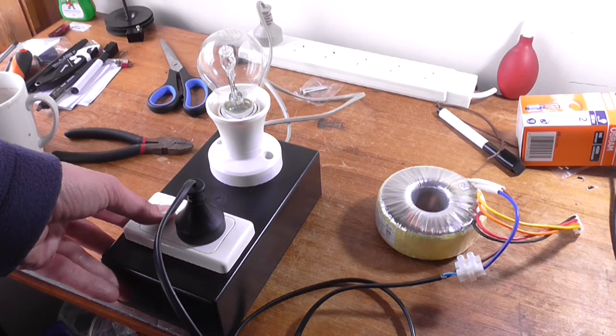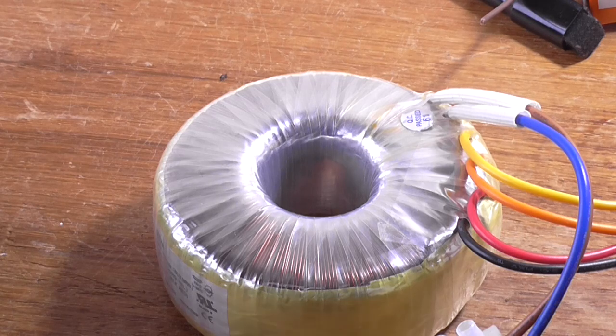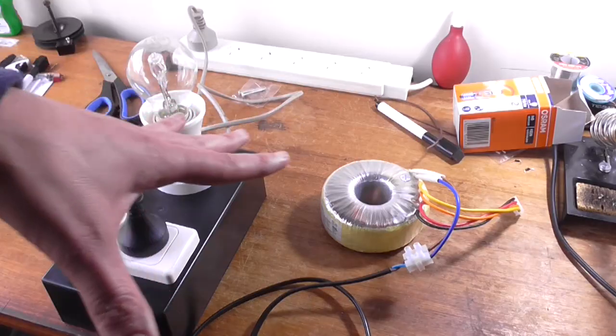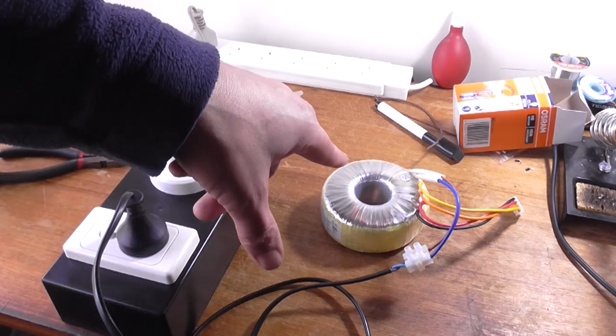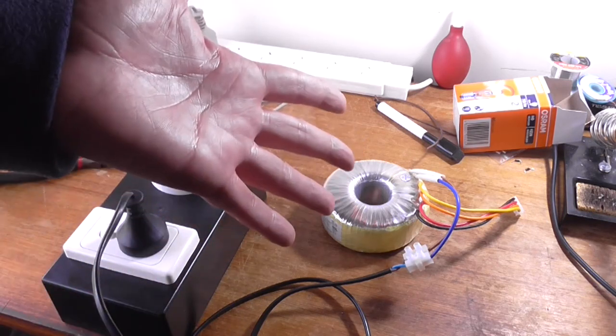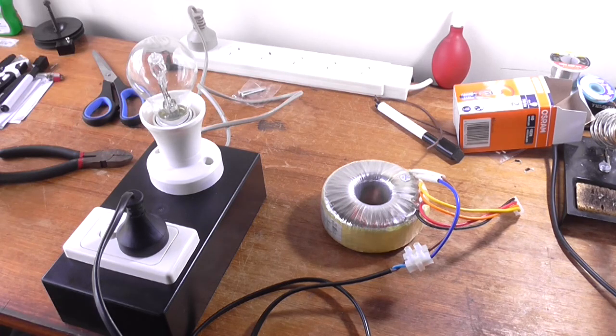Didn't even see anything, I can actually hear it humming. Indeed, but there was very little inrush current with that transformer not loaded on the secondary. However, if I load it up on the secondary, we might see something a little bit different.